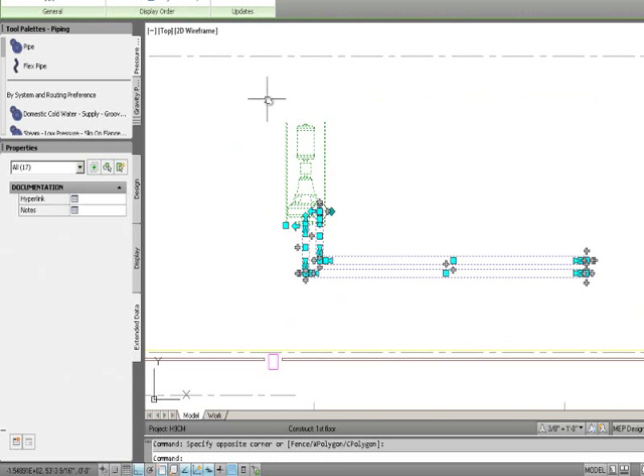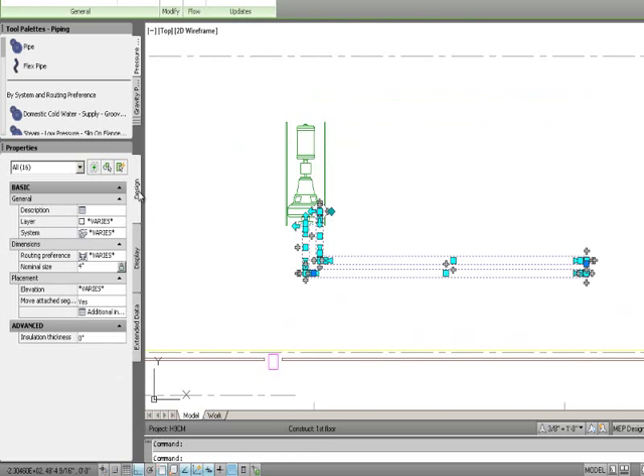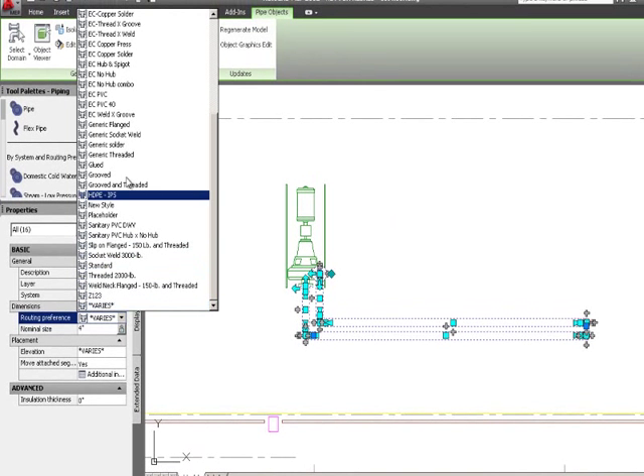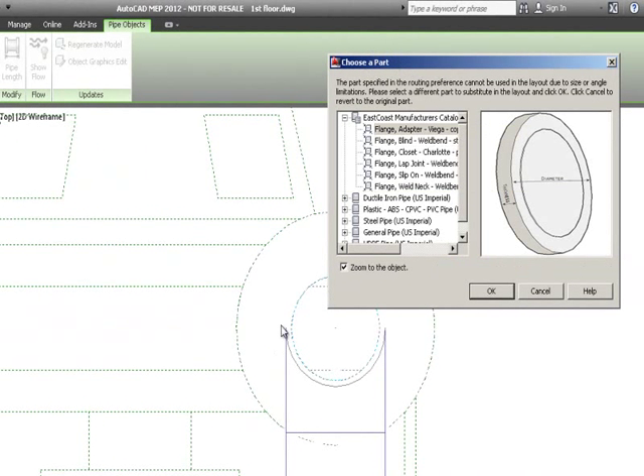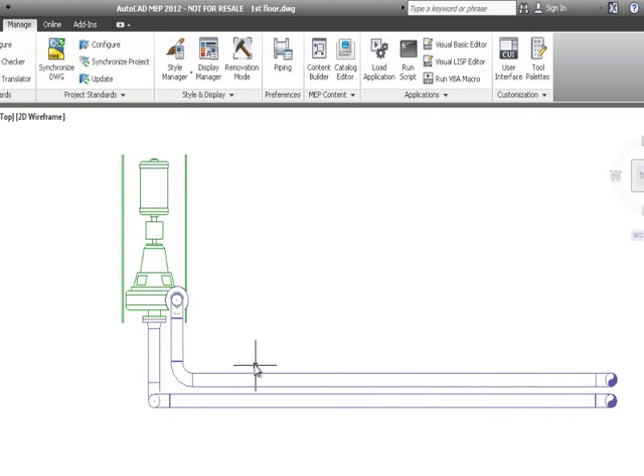If I select everything except the pump and go back to my Design tab, I can change the routing preference to the EC thread-by-weld we just looked at. The system goes back through and replaces the fittings with the ones selected in that routing preference. It also sees a flange and asks what type of flange to use — I'll answer that I want a weld neck flange. That switches everything out.